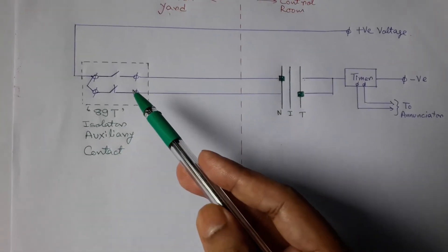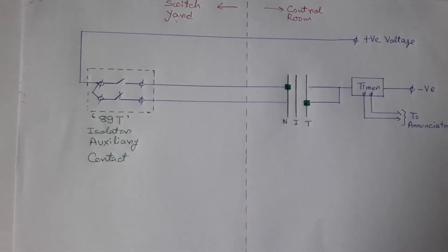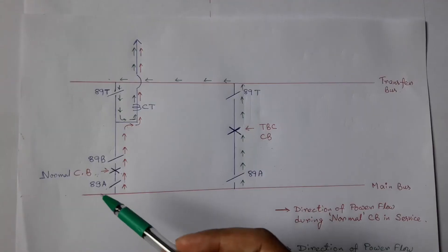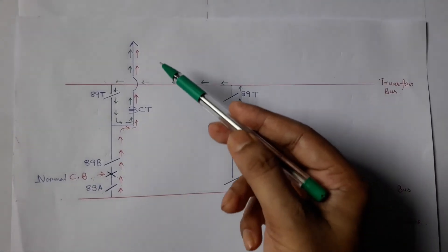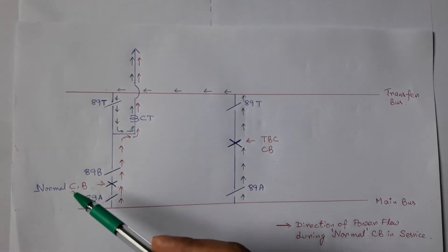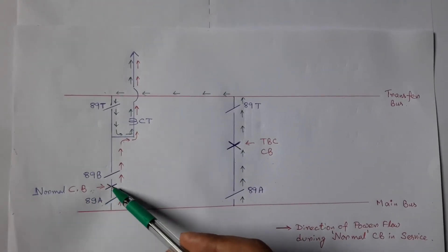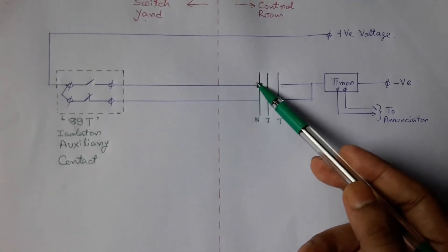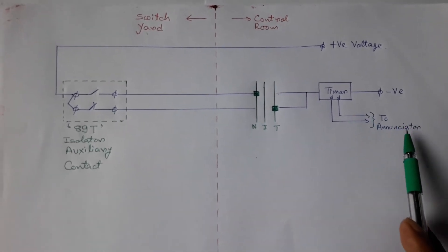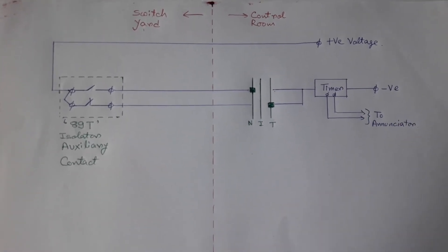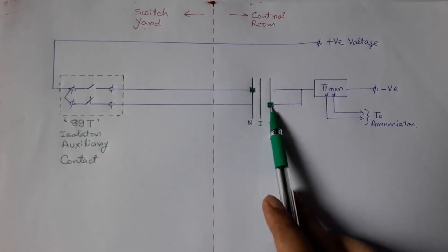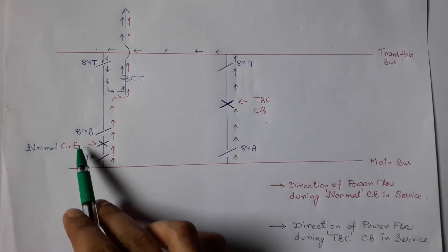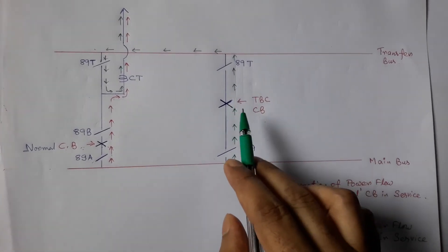The contact configuration of the auxiliary contact of the 89T isolator is as shown, and the positive voltage will appear at this terminal. But as the normal circuit breaker is in operation, during a fault in this line, our goal is to trip this circuit breaker only, not the TBC circuit breaker. So we will put this switch in normal position, but if accidentally we put this switch in transfer position, then there will be an audible annunciation.